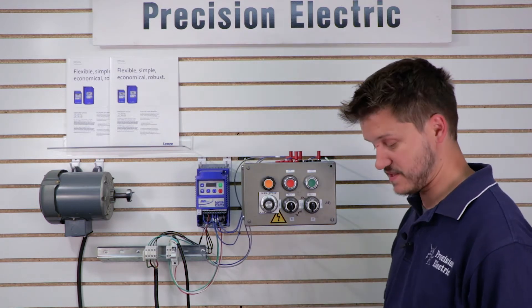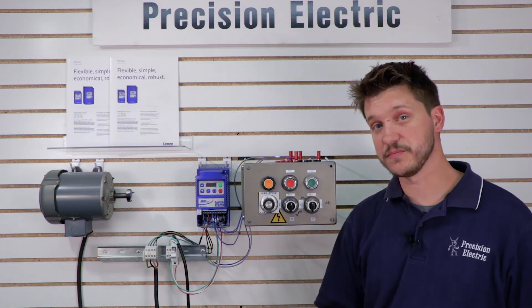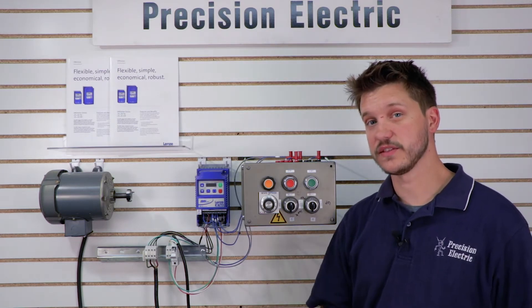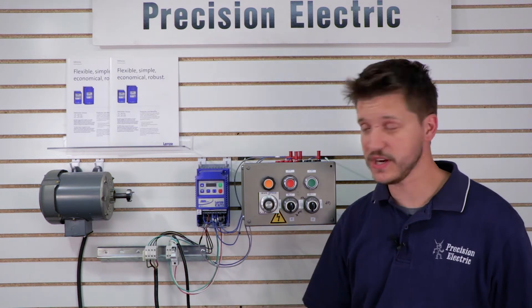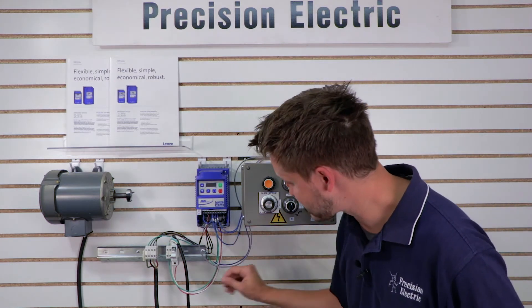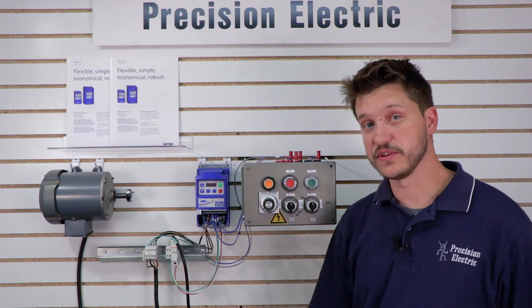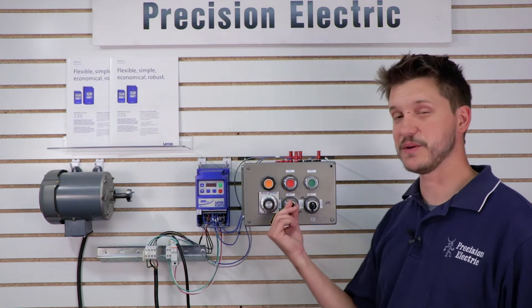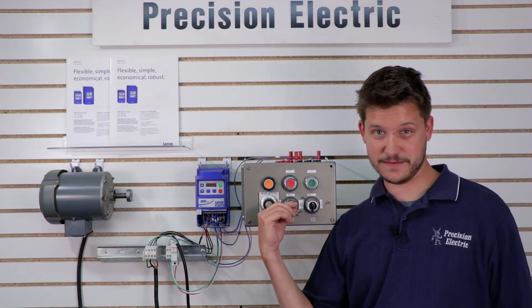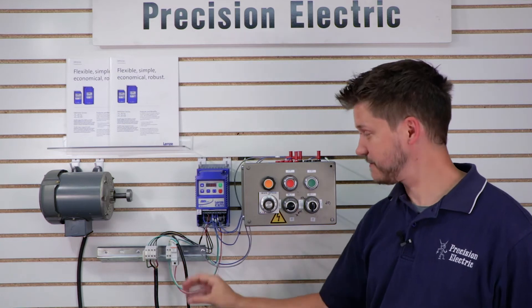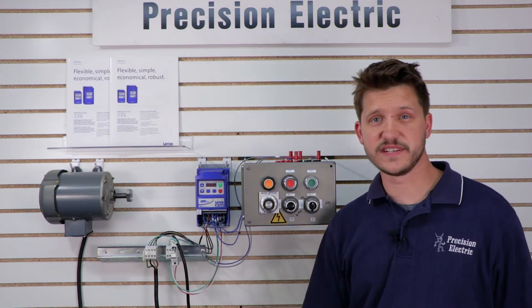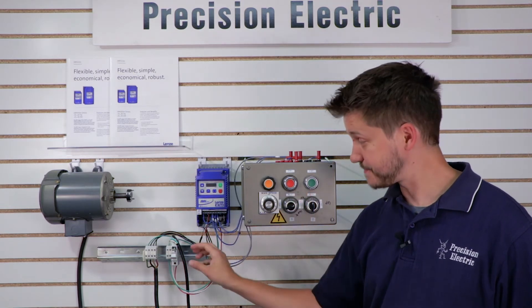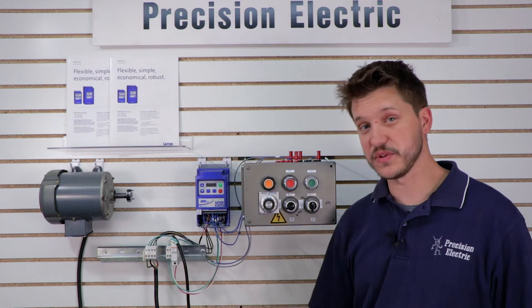The first one we're going to go over though is number one, which is start on powerup, which means that if I set parameter 110 to one, the drive will actually start as soon as I apply power to the drive. And here is an example of that. I'm going to apply power to the drive. I've already pre-programmed 110 to start on powerup. Notice it didn't start, but that was just because I didn't have my run command. That's an important lesson actually to take from this is that it won't start on powerup if you don't have some kind of a run command programmed for it.